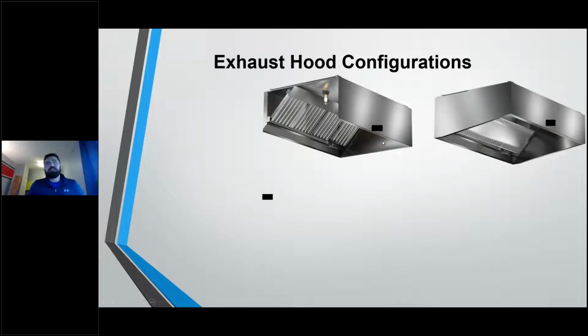Now, the next configuration is going to be a wall canopy hood, but a tapered front. So these hoods are required per ADA to be hung 80 inches above the finished floor. But if you're doing a renovation or if you have a lower ceiling application, there may not be a scenario where you can hang this hood 80 inches above the finished floor and then have a 24-inch box on that hood. You may need a lower ceiling requirement.